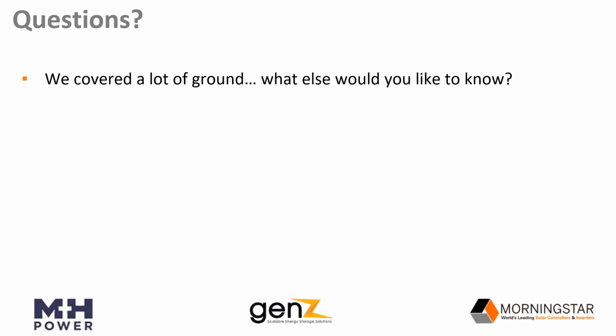And back to Brad with this next question. Can I have multiple Morningstar chargers connected to the same battery bank, and how many of them, and do they communicate with each other? Okay, yeah, excellent question, since we're talking lots of parallel applications and scale. With our current line, we do not have inter-controller communication. In other words, multiple controllers do not intercommunicate with each other and synchronize. However, we do have a fairly well-written explanation of the things to take into account when you are paralleling charge controllers, because it can be done just fine.